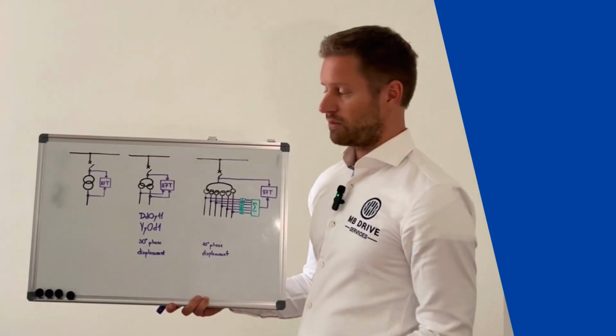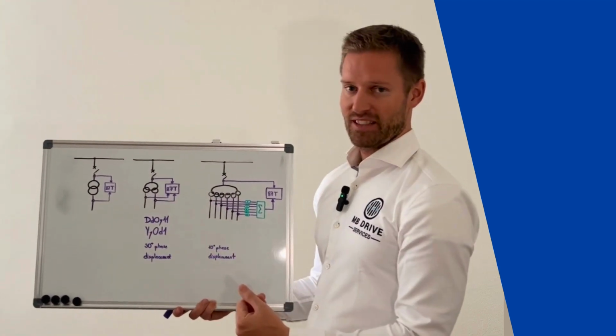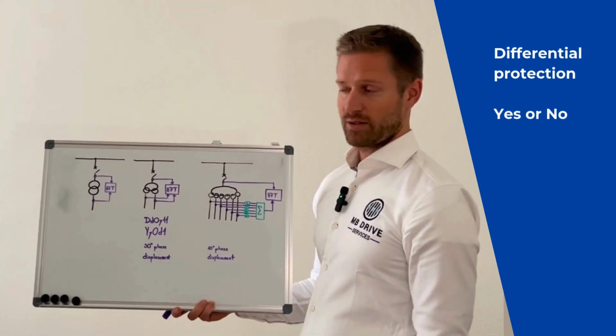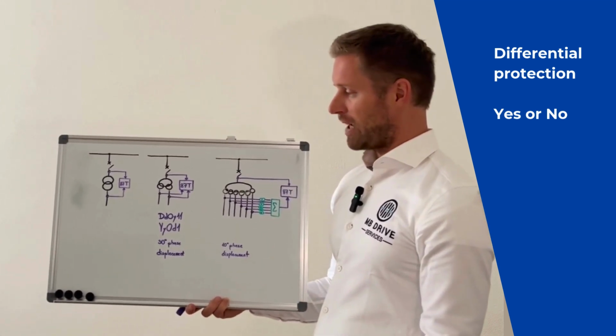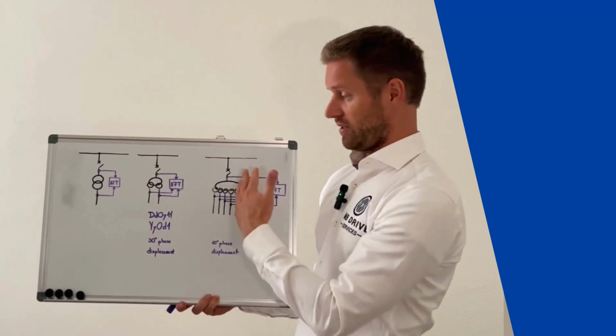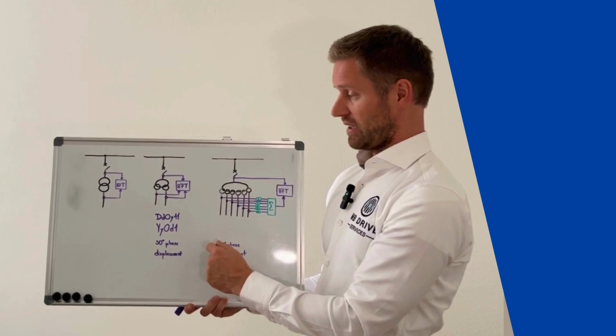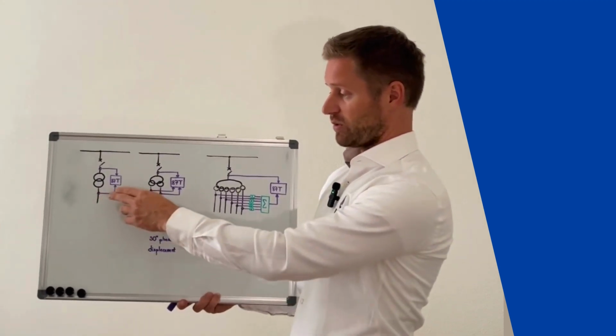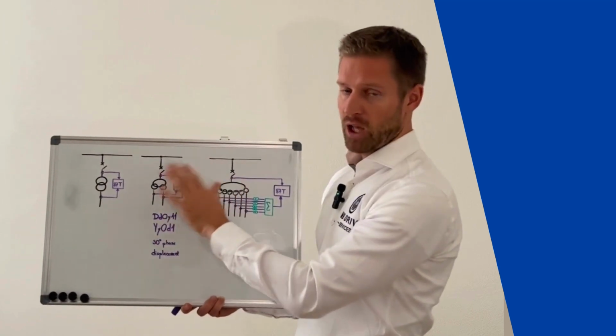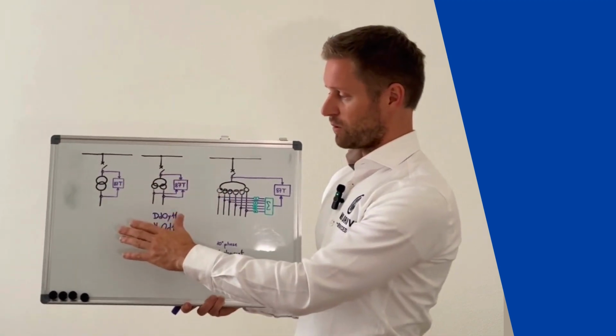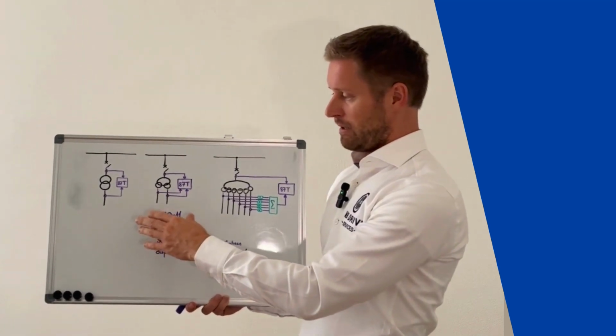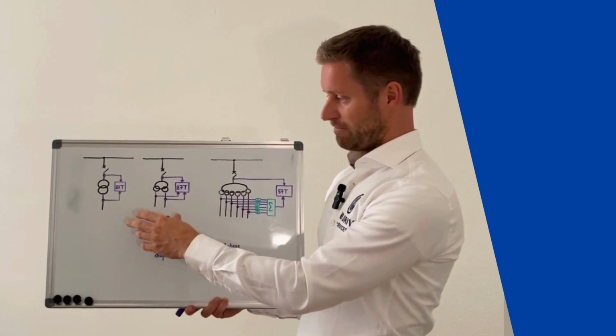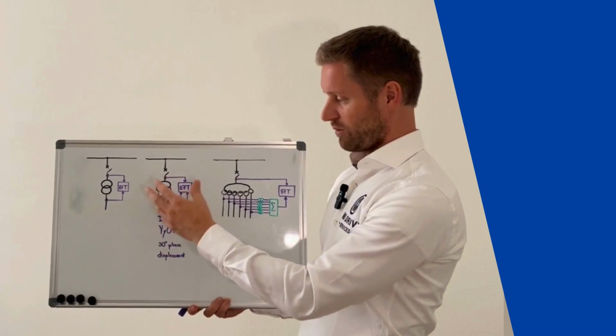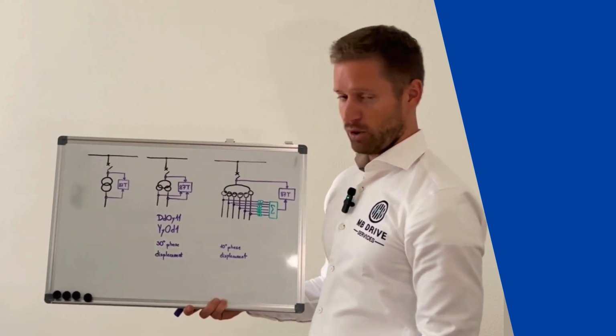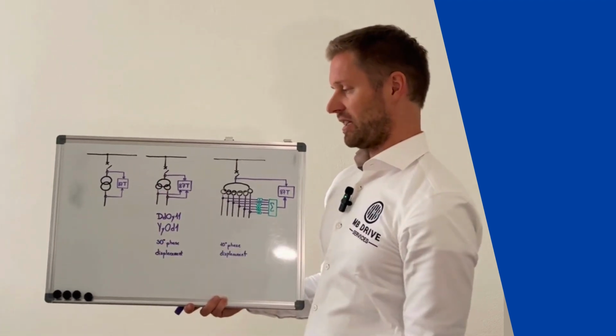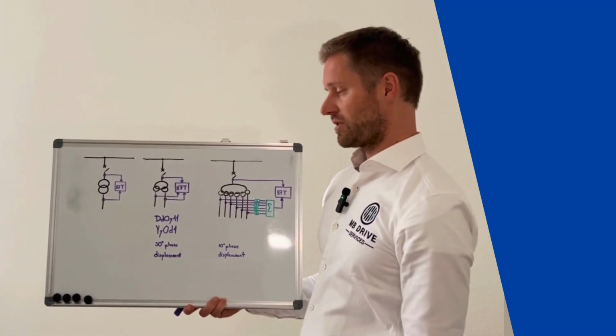So generally, if you would ask me, back to the original question, differential protection on a VFD transformer, yes or no? I would say it's not black and white. It really depends on the topology of the VFD and the corresponding transformer design. If the transformer is simpler, like 2 or 3 winding, okay, no problem. It's very straightforward. The implementation is easy. The probability of some wrong implementation or wrong parametrization is relatively small. So there I would say it's for sure an option to consider.